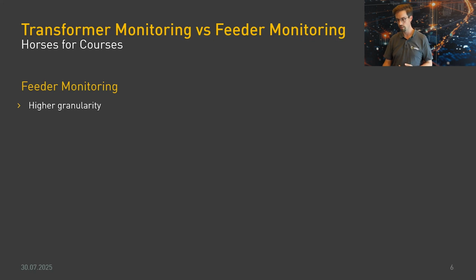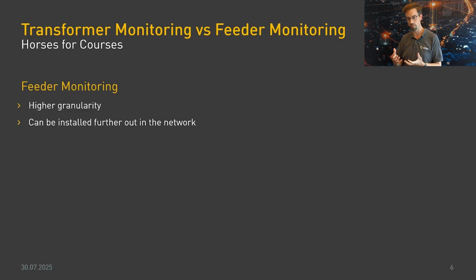So starting with feeder monitoring. Feeder monitoring gives you just simply a much higher granularity. So you can imagine you have your transformer station, you have a transformer, and you maybe have anything between, say, 4 and maybe 10 feeders coming off of that. If I can measure, say, those 7 feeders coming out of there, and I can understand what the load distribution is across those feeders rather than the single point of the transformer, I have a much better granularity of information about what's happening in the network below that. So that's the first situation, where I need high granularity. Feeder monitoring is the better solution.